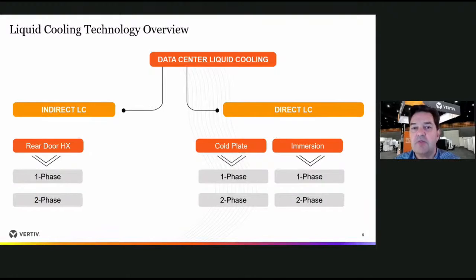Navigating the technology available for liquid cooling, it's important to understand the variation between indirect and direct liquid cooling. Indirect liquid cooling is where we're not taking the liquid directly to the IT; we allow for an interface, typically a rear door. Technologies available include single phase and two phase. By two phase, I mean the liquid or fluid coming into contact with the heat load is changing phase, typically through a low boiling fluid that boils at about 49 to 50 degrees C, well below the temperature of the hot devices. Through that phase change, the cooling process is benefited.